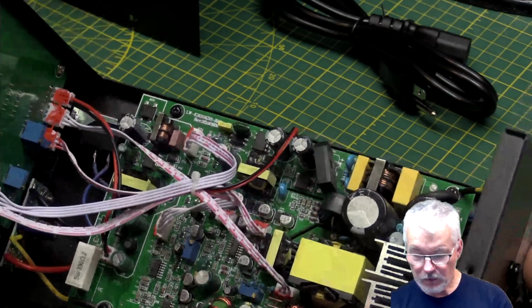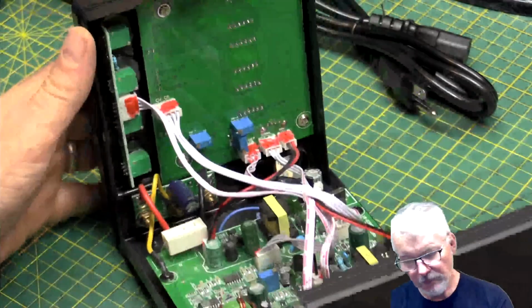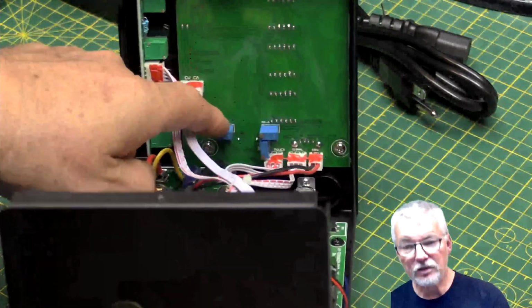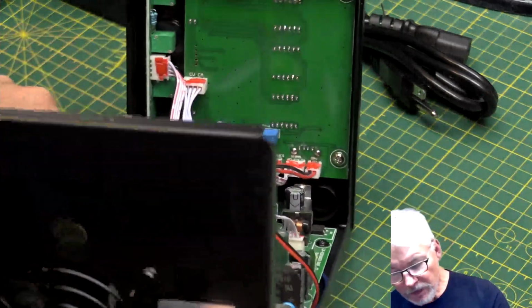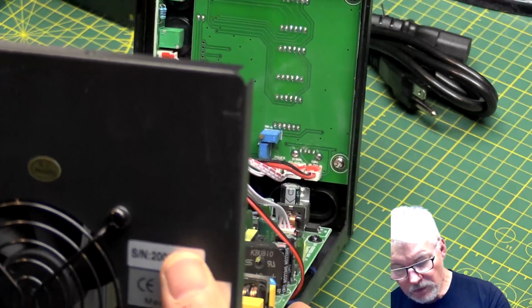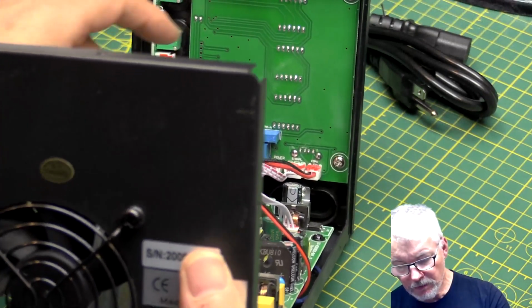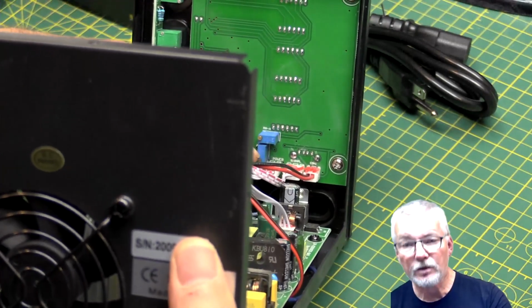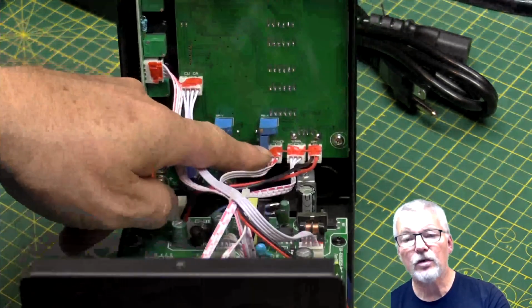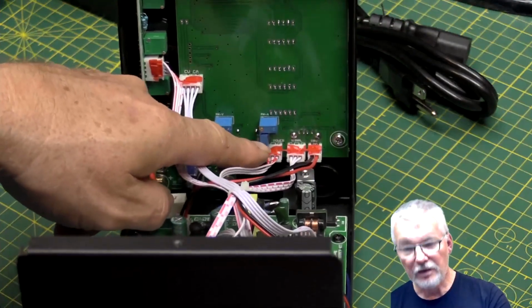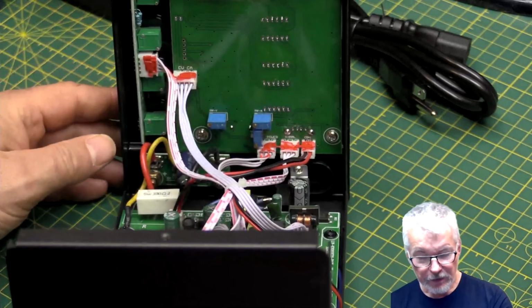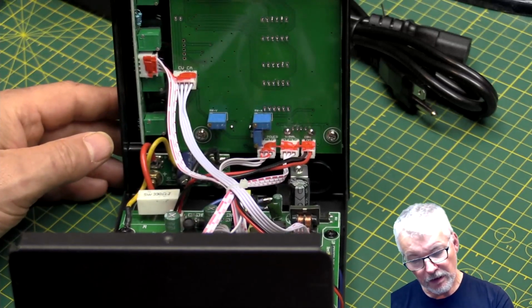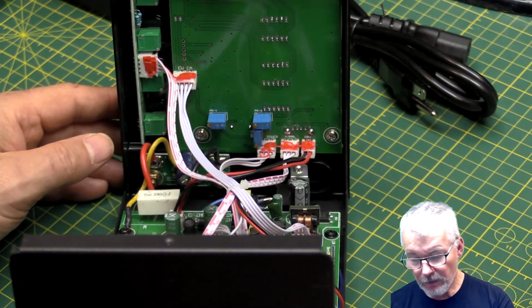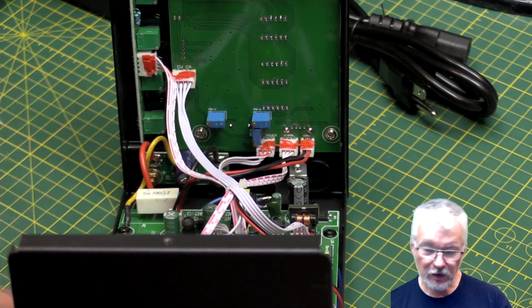The board certainly looks well made. We do have a couple of calibration points here, 10-turn potentiometers. This one is for the volts adjustment, we've got current adjustment, and we have a zero adjustment down here. Sorry, I keep blocking them with the thing. So potentially you could adjust these to bring them more in spec. We'll have a look at that again.